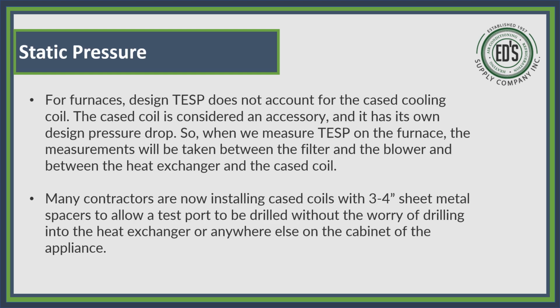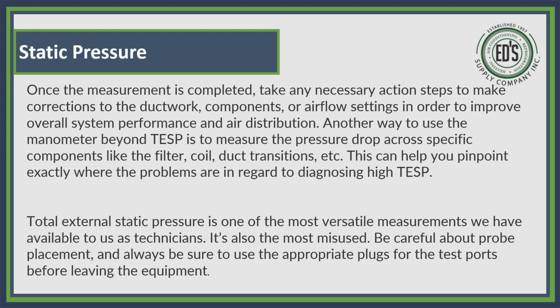Now, for furnaces, the designed total external static pressure does not account for the cased cooling coil. The cased cooling coil is considered an accessory, and it has its own design pressure drop. So when you measure total external static pressure on the furnace, the measurements will be taken between the filter and the blower and between the heat exchanger and the case coil. Many contractors are now, like I said, installing a case coil with 3 to 4 inches of sheet metal spacing to allow a test port to be drilled without the worry of drilling into the heat exchanger or anywhere else on the cabinet of the appliance. It's always a good rule of thumb, if you're building the ductwork and you're able to do that, you can actually put that in between the cabinet itself and the actual coil. So you want to keep that in mind as you're designing your ductwork.